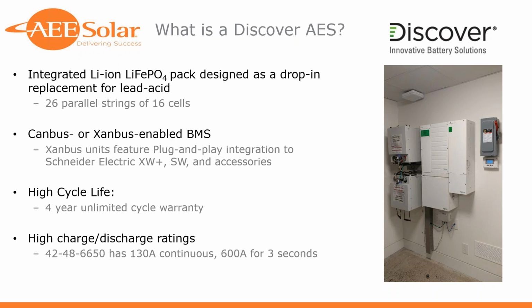The installer's also done a great job at putting a lot of this stuff behind the wall. So you don't see a ton of conduit going from the XW Plus to the disconnect. You see there, he's got some looming to do on the communication wires from the packs back to the comm box, but very tidy, a really small footprint for the usable energy he's going to get.